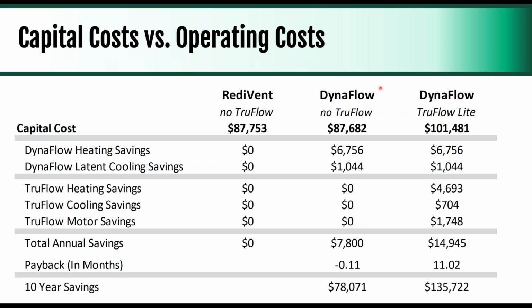So just by going high efficiency hoods, in this situation you're saving about $80,000, whereas with the demand control, that almost doubles the number to $135,000. So again, pretty significant savings.